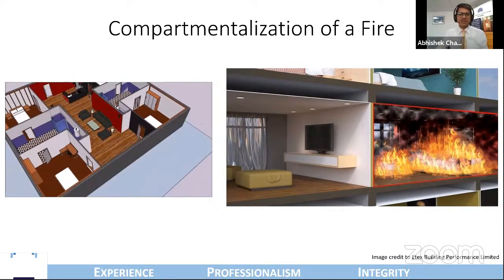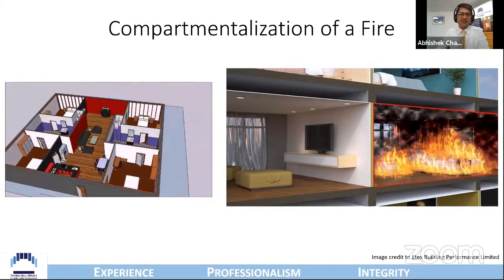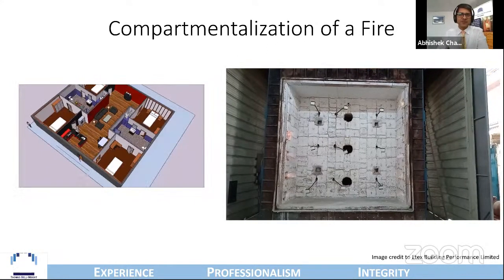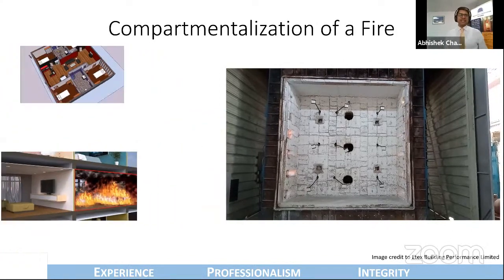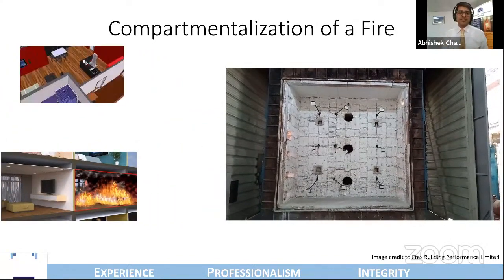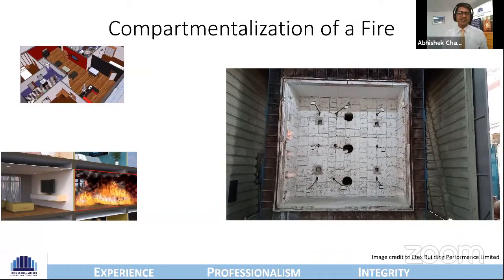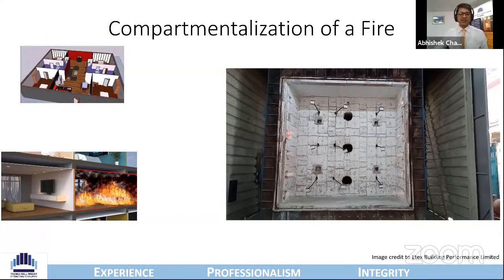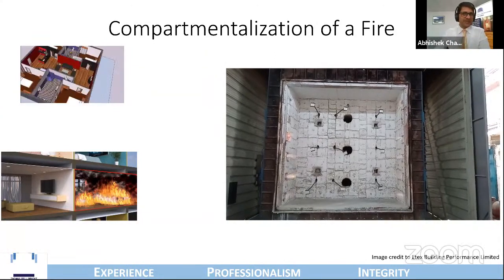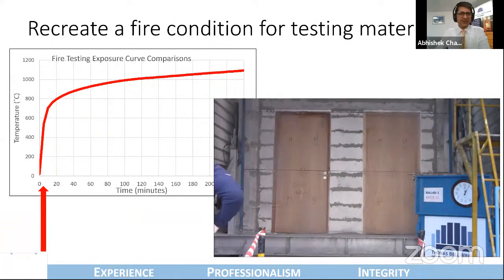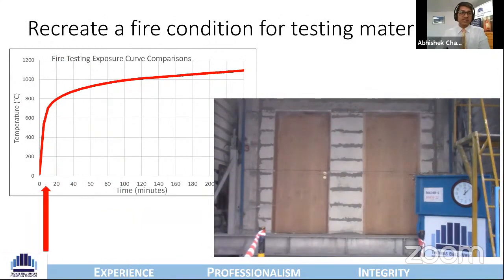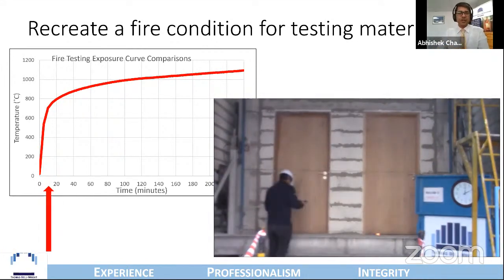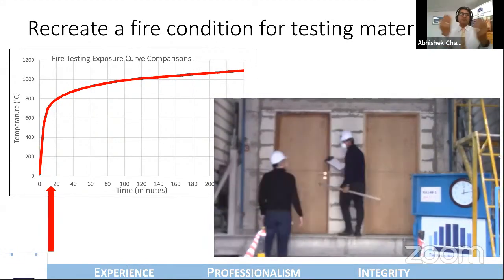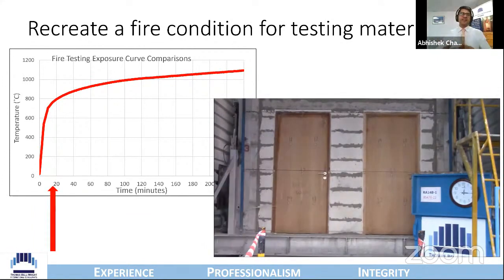But first, how do we really test anything that is able to deliver this containment? What you see on your screens is an image of a furnace, where a fire resistant element is tested. This furnace is from our laboratory here in Dubai. What we typically do is install the compartmentalization system, in this case a fire rated door, which closes the face of the furnace you just saw.